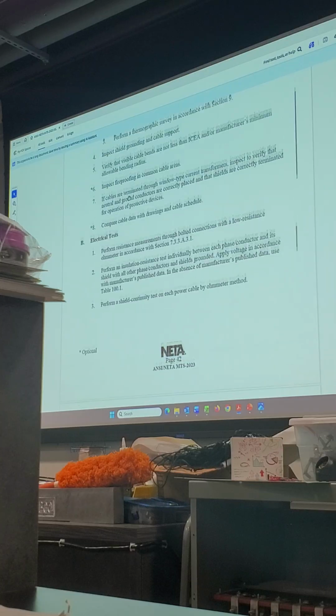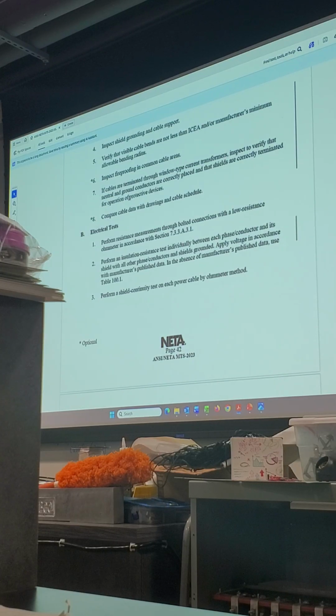Inspect exposed sections, inspect terminations, splices, bolted electrical connections. What we're interested in here is the electrical tests, because we're talking Megger DLRO, Megger Ductor. Perform resistance measurements through bolted connections with a low resistance ohm meter.